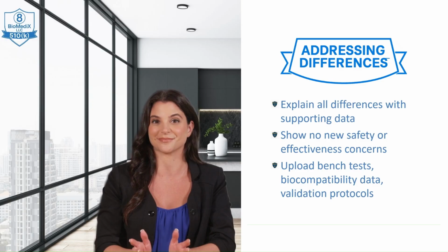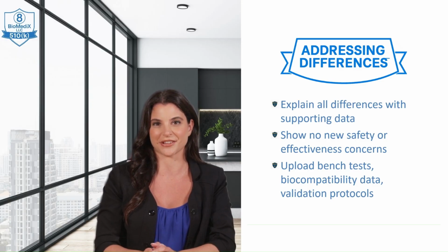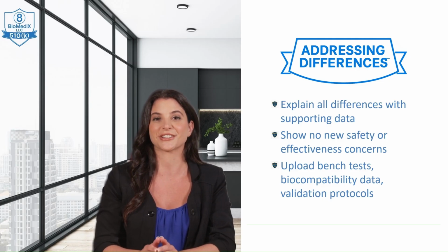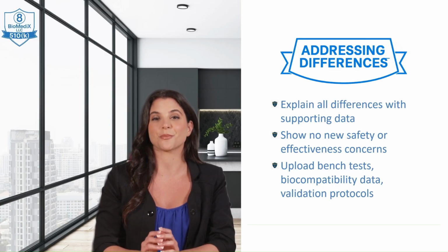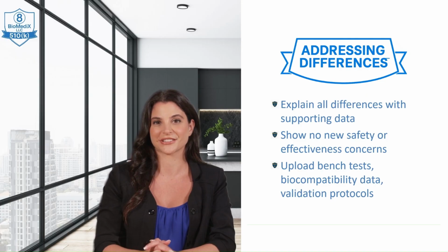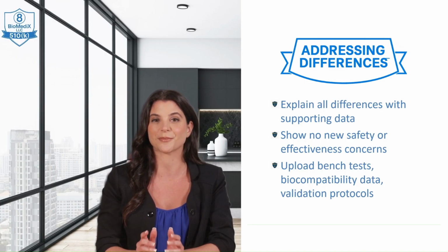Addressing differences. Any differences between your device and the predicate must be thoroughly explained with supporting data, demonstrating that these differences do not introduce new questions of safety or effectiveness, and that your device is as safe and effective as the predicate. For example, if your material is different, you must explain why this does not introduce new risks, using uploaded attachments like bench testing, biocompatibility results, or literature summaries.